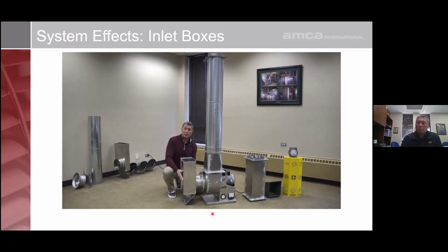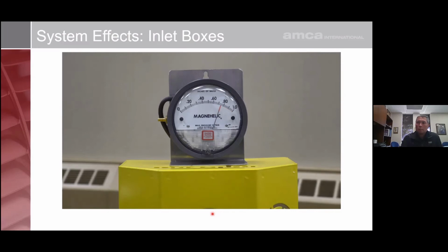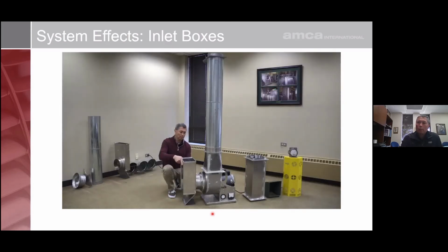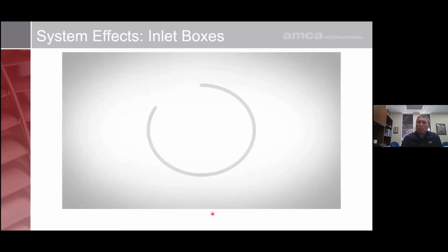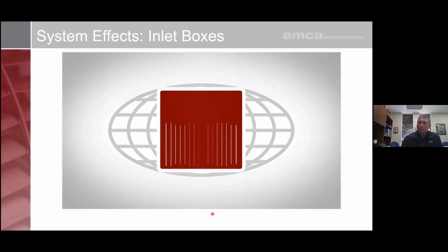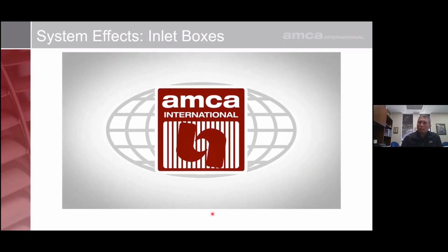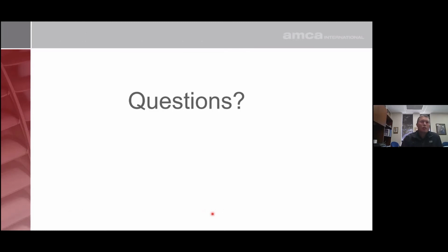Put this onto the inlet of the fan, and you'll notice that, yes, we do have a loss associated with the inlet box, but it's much less than the improperly designed inlet box losses. Any questions on inlet boxes before we move on to straight runs of ductwork at the inlet of the fan?